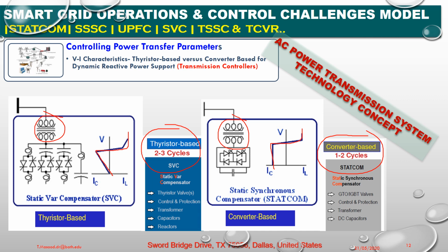Okay. The STATCOM can be operated over its full output current range even at very low voltage, theoretically, typically about 0.2 per unit value. In other words, the maximum capacitive or inductive output current of the STATCOM can be maintained independently of the AC system voltage, and maximum VAR generation or absorption changes linearly with the AC system voltage. So it can go to full capacitive and full inductive mode of operation. So this one is the full capacitive mode of operation, and this is the middle here, and on the left side it will go to capacitive mode of operation, and on the right side it will go to inductive mode of operation. Similarly, for the SVC, the left side will go to capacitive mode of operation and the right side will go to inductive mode of operation.